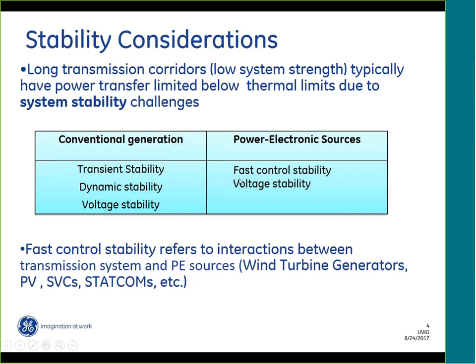And then we're going to see an example of this. Then the other type is voltage stability. You will see that from comparing the right and the left of this, basically transient stability is typically not a significant concern for power electronic sources. Although sometimes we use transient stability tools or stability tools, we're typically trying to assess the voltage stability in that case. And then dynamic stability, which is associated with the exchange of energy between rotating masses connected in electrical systems. That's also not of concern in power electronics because the masses of these sources, in the case of wind turbines, the masses of the wind turbines are really decoupled from the operation of the grid to a large extent. So when it comes to stability, this type of sources have system stability issues, and they manifest themselves differently than with conventional generation.